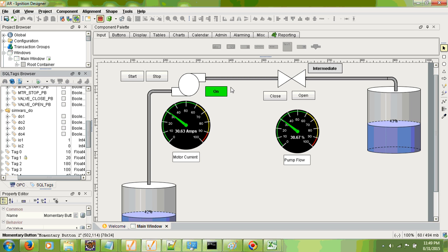There are also two integer outputs to represent the multistate indicator. One is for the pump — to indicate on, off, and trip condition — and the other indicates whether the valve is fully open, fully closed, or in an intermediate state. The number can be zero, one, or two indicating whether the pump is off, on, or tripped, and IO2 represents the valve as fully closed, intermediate, or fully open.